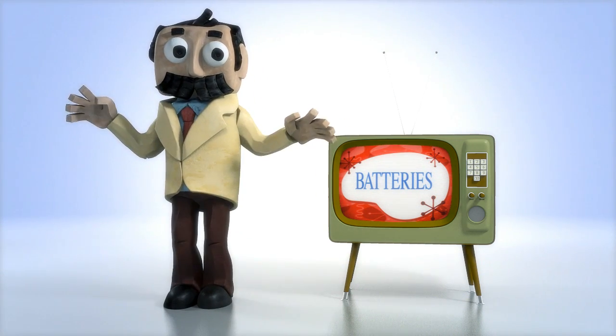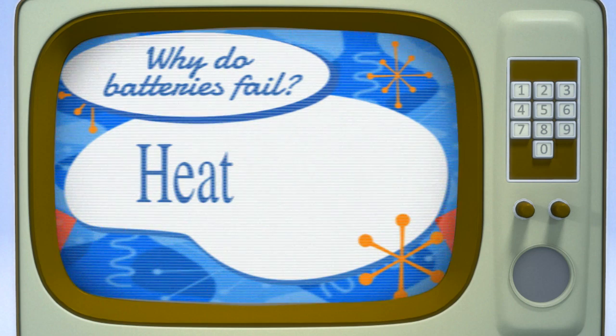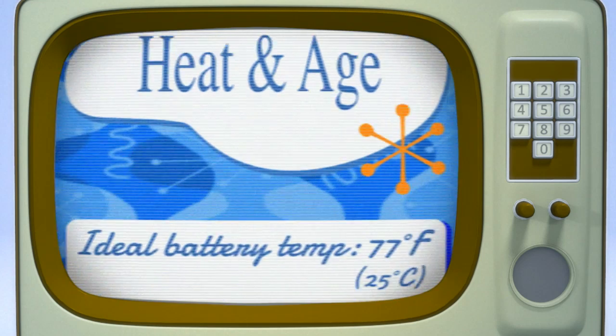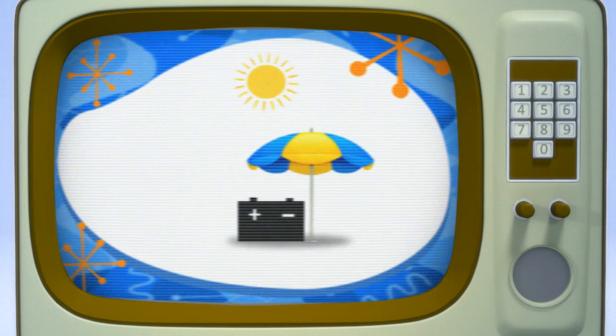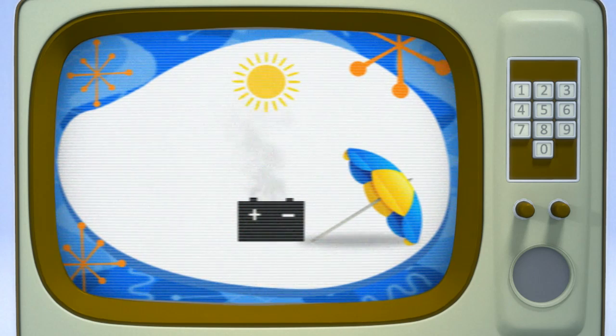So, why do batteries fail? Heat and age are the primary factors. Batteries like to be kept at 77 degrees. Any warmer and battery life will be greatly reduced. Keep your UPS in a temperature-controlled environment. If it's too hot for you, it's probably too hot for your batteries.